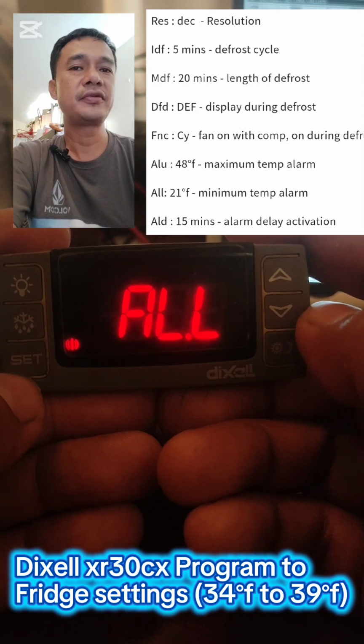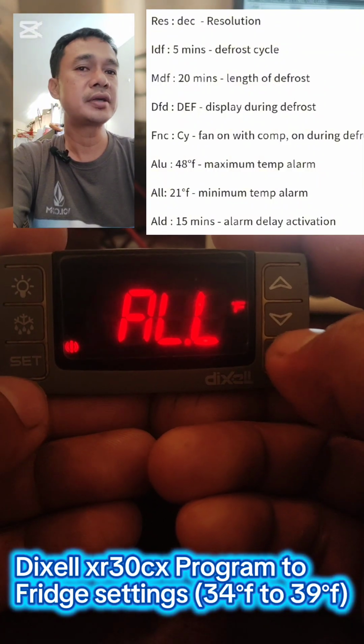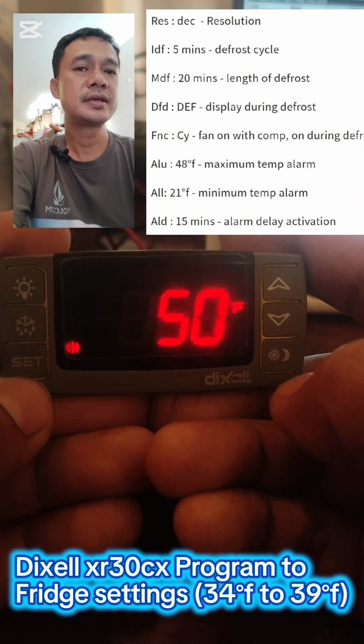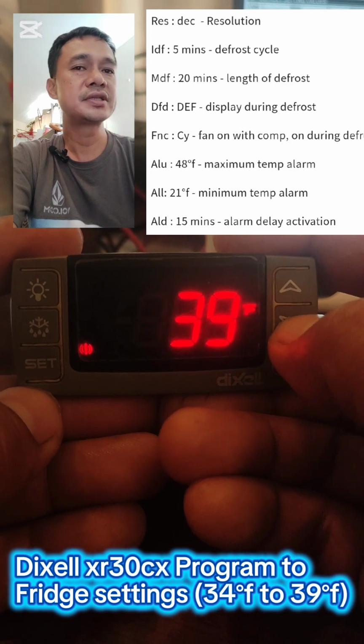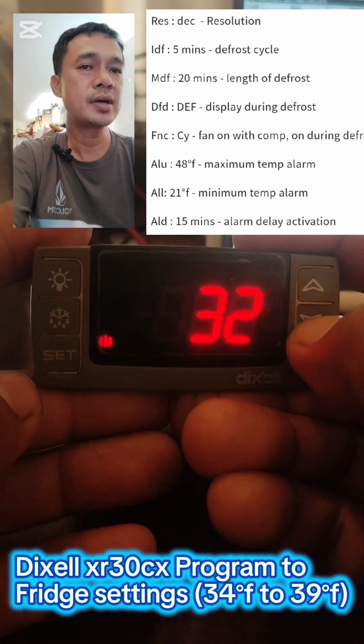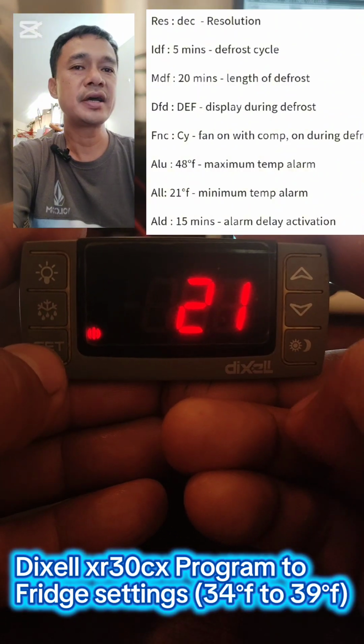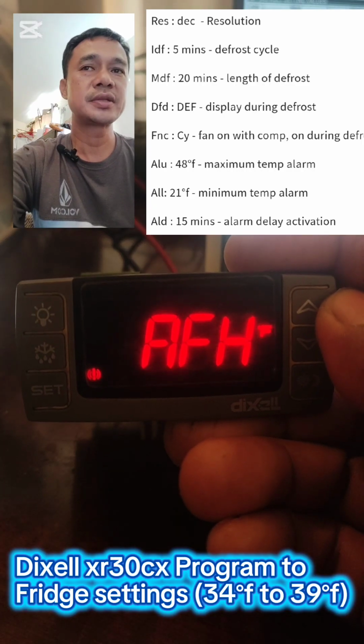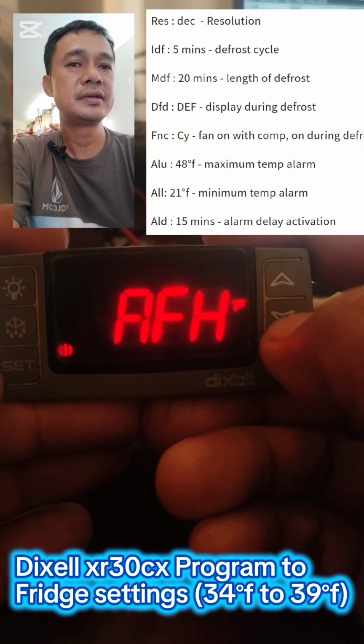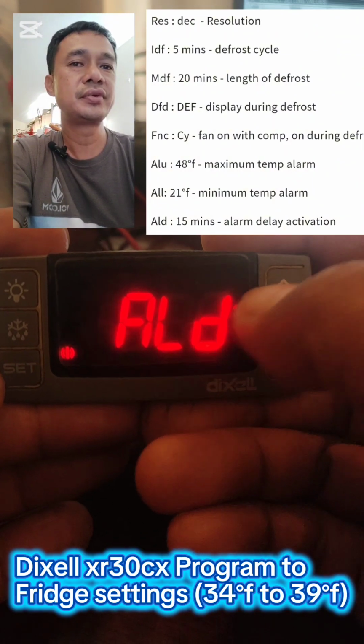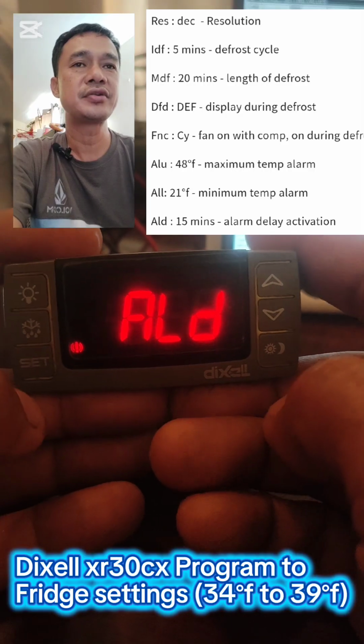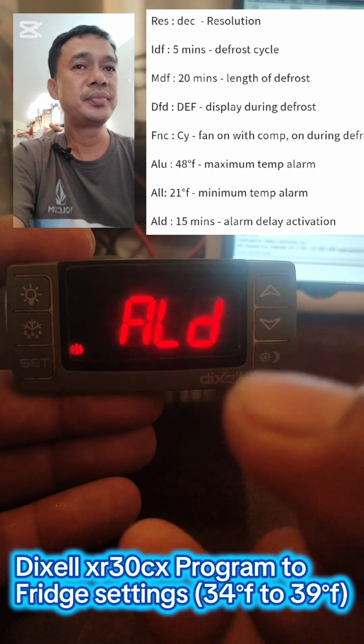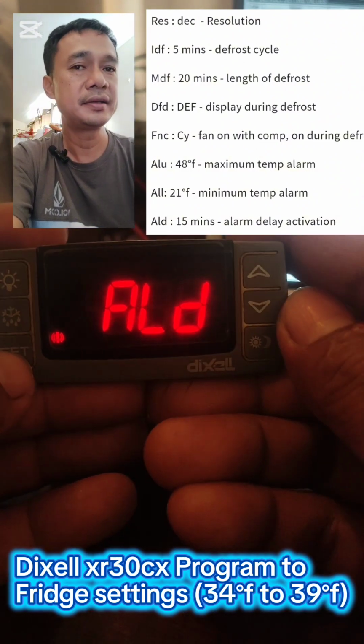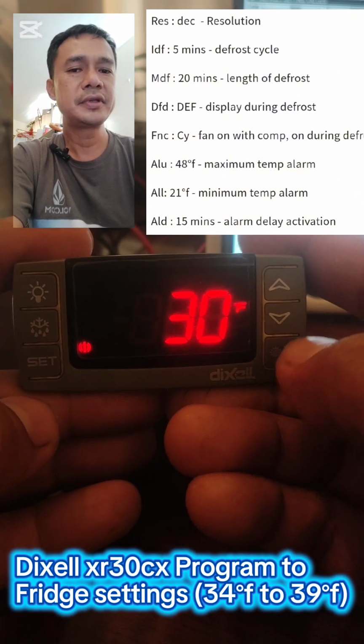And ALL stands for minimum temperature alarm. Press set, and I'm going to reduce this to 21 degrees Fahrenheit, since my lowest set point is 34 degrees. I just add with it. And next for this, let's go to ALD. We're going to delay the activation of the two alarms, the ALU and the ALL.